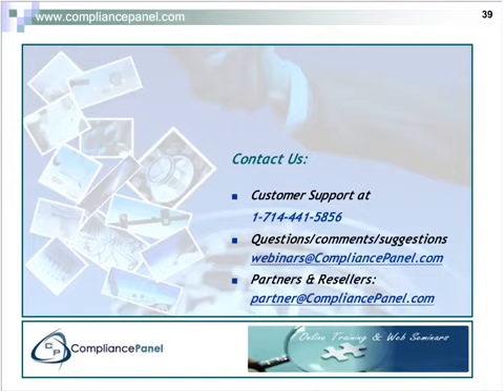If you're marketing direct to clinical use devices, there is the MDR, the medical device reporting process, much like the vigilance process for Europe, if you're familiar with that. That would be how the FDA would expect you to handle your complaints. That's the only thing I see as different. But again, you can get those requirements right out of 21 CFR 820 without going through 13485.